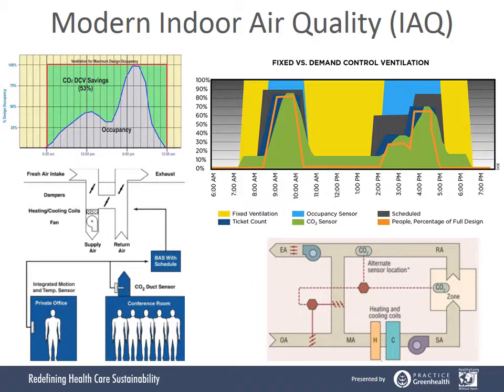For about the last 20 years, we've had demand control ventilation technology, where we measure air quality by proxy and control the air so we're putting ventilation where it's needed and when it's needed. We do this in classrooms, dining rooms, meeting rooms, movie theaters, and lab spaces. I've seen a lab building with a multivariable real-time air quality control system that controls contaminant levels and modulates exhaust based on wind speed. Very cool HVAC technology—but we don't use any of that tech in healthcare. That 2 air change number back in the table just excludes us from using any of it.